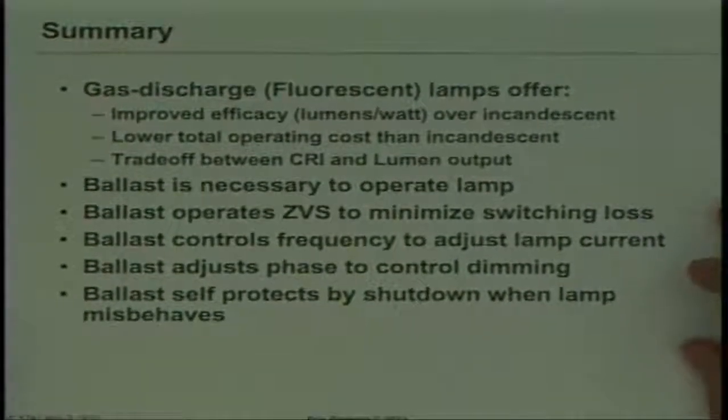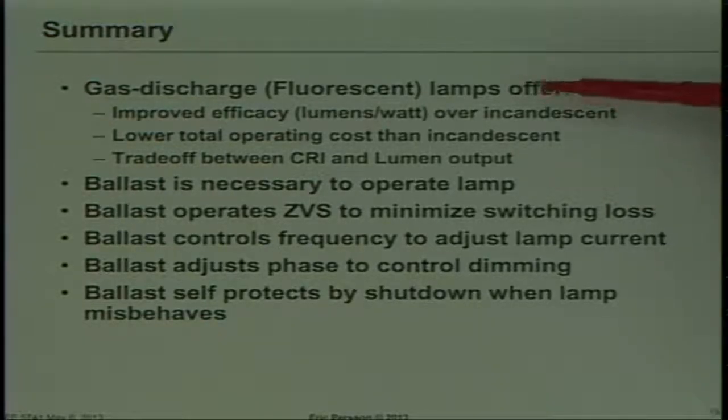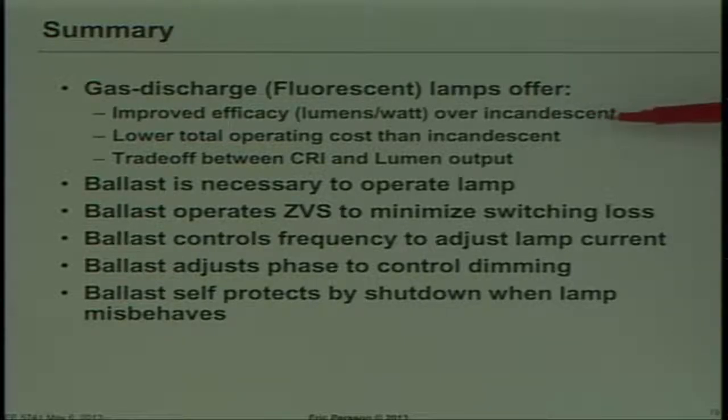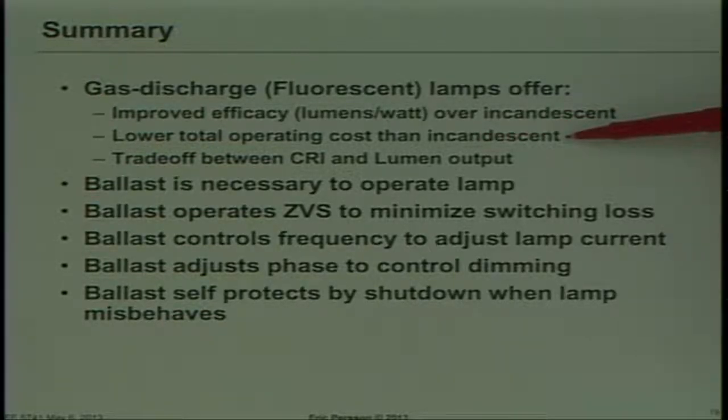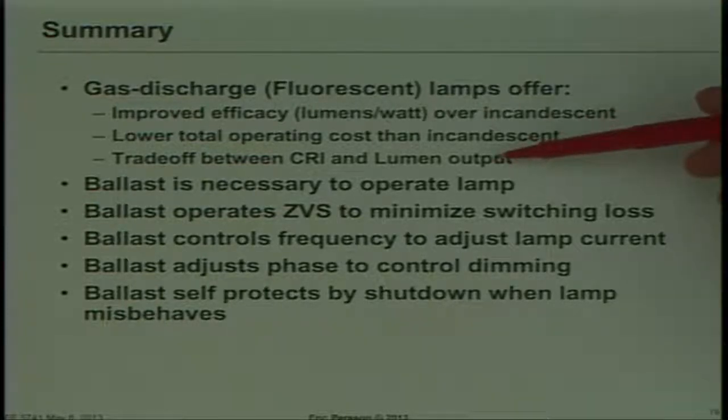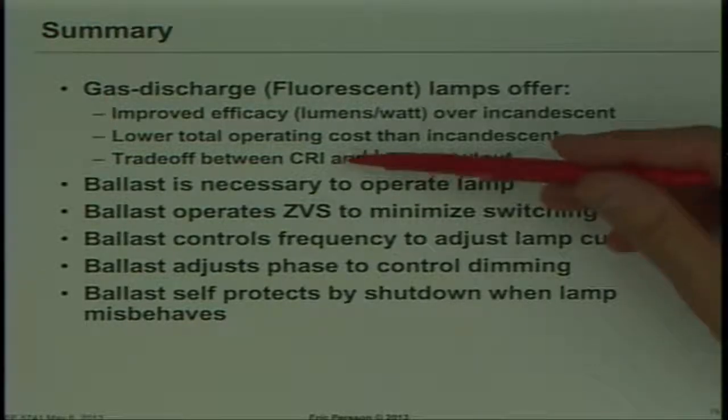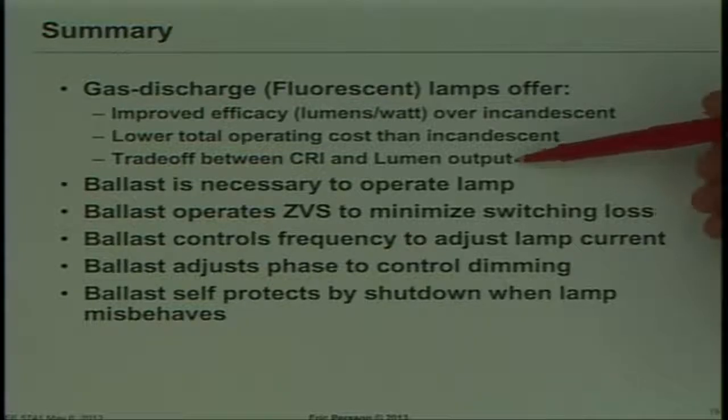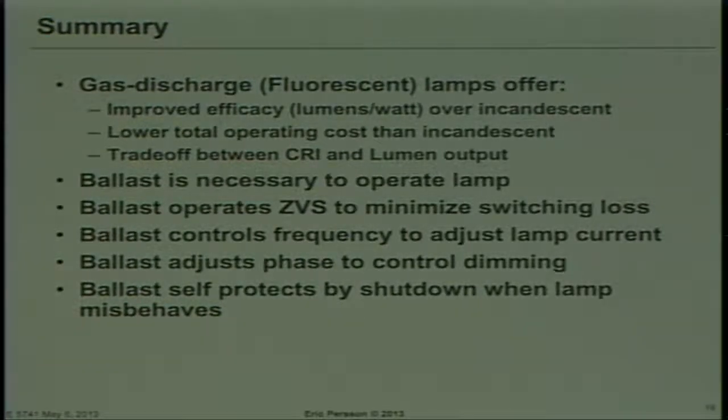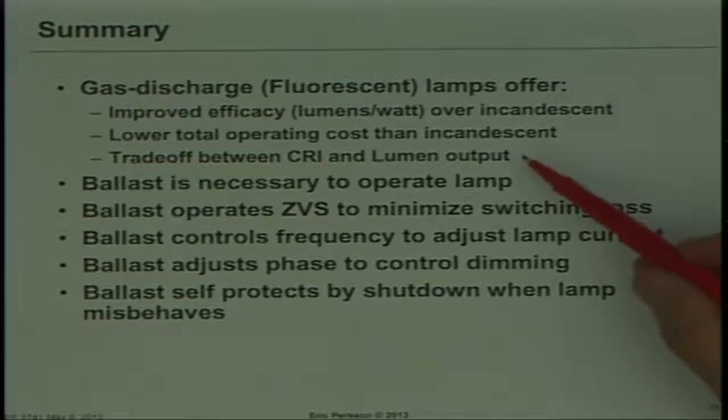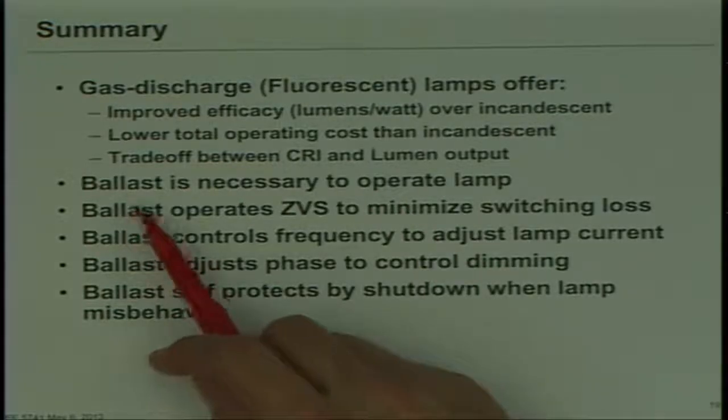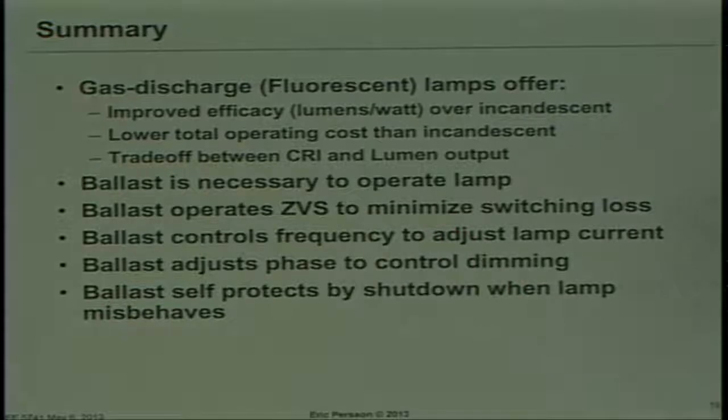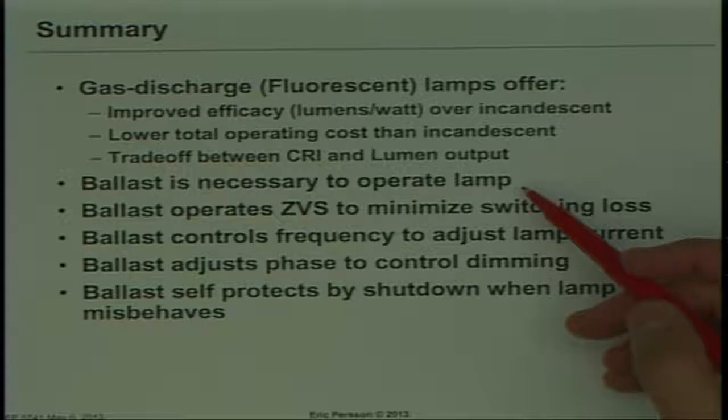On the fluorescent lamps, summary is the fluorescent lamps give you improved efficacy, which is lumens per watt compared to incandescent. Theoretically, have a lower total operating cost than incandescent if you amortize the initial high cost over the longer lifetime. But there's a trade-off between color rendering index, how your eye perceives the light, and the lumen output. If you've seen what we call the cool fluorescent lamps that have the highest output, they're not very pleasant to look at. It's a kind of a harsh light characteristic. That's the trade-off. The lamps need a ballast in order to operate because of all the operating modes. They have to go through a preheat mode, a strike mode, and an operating mode.